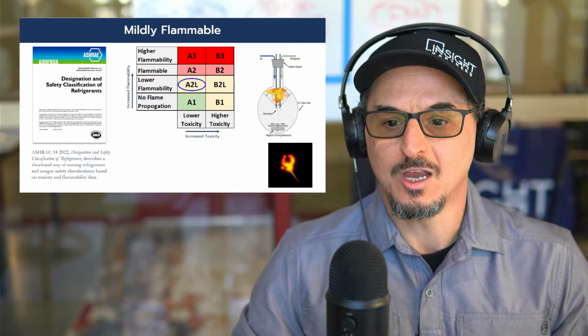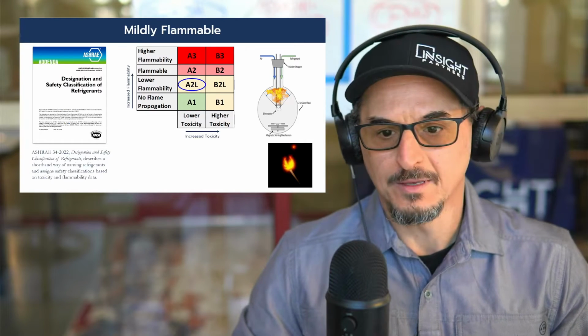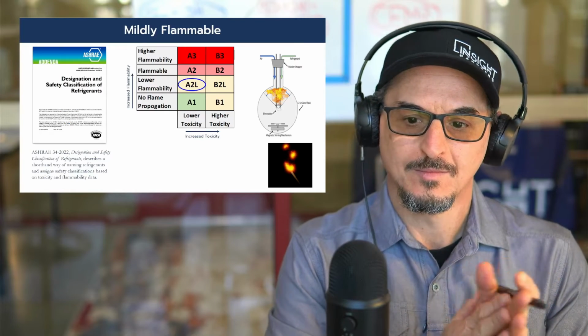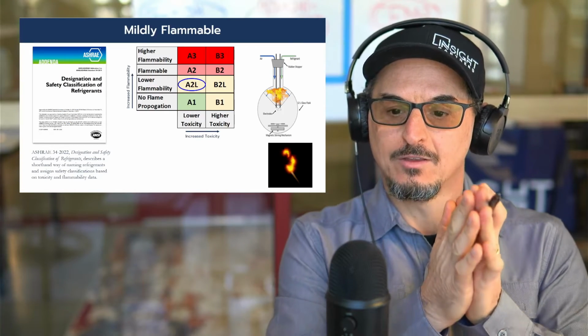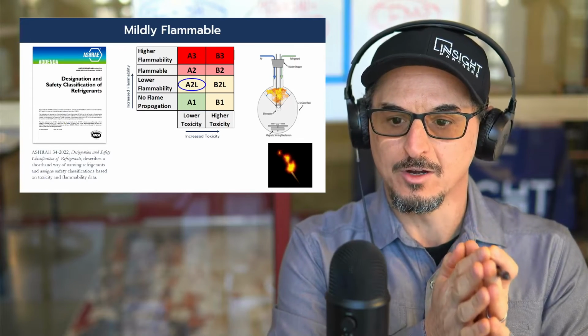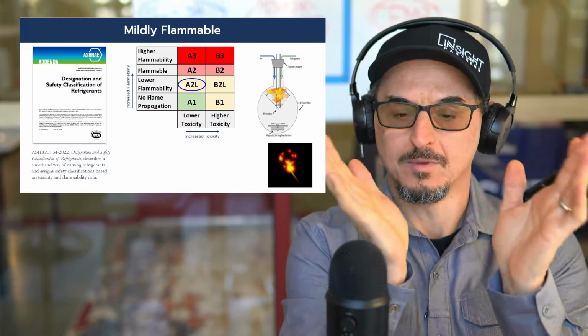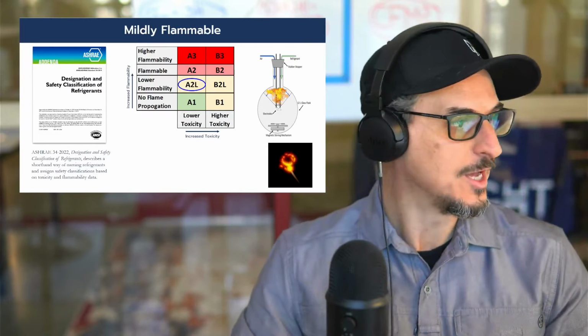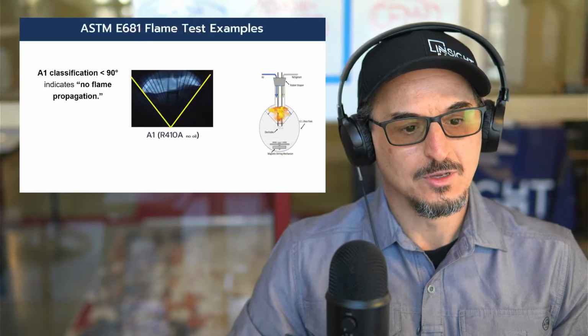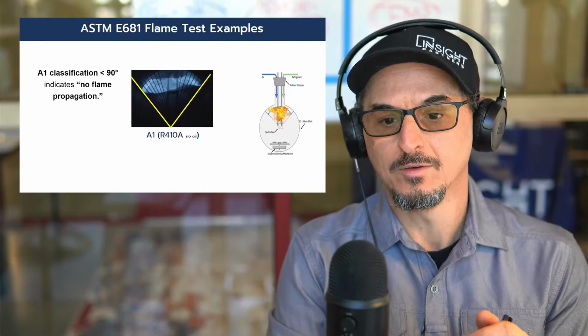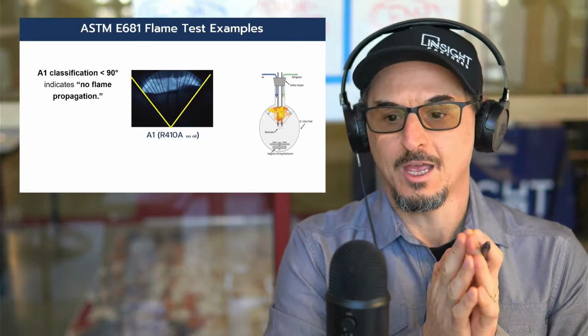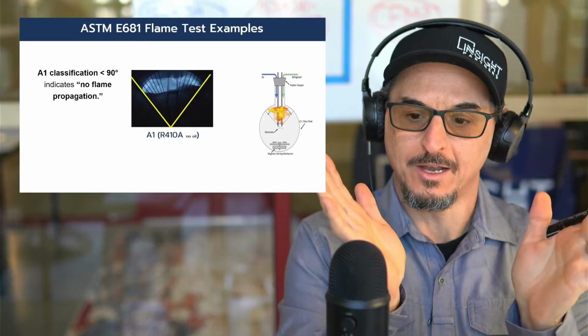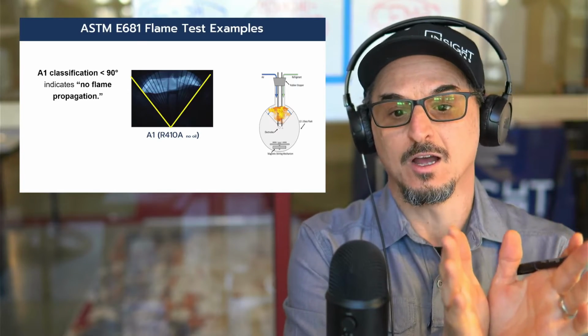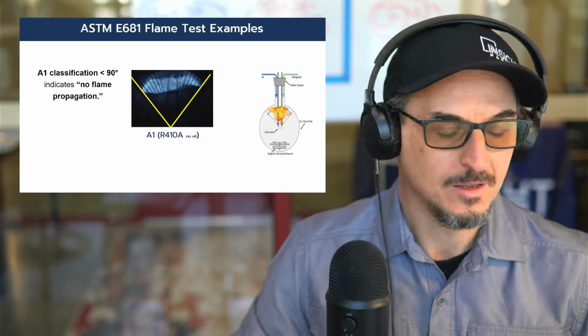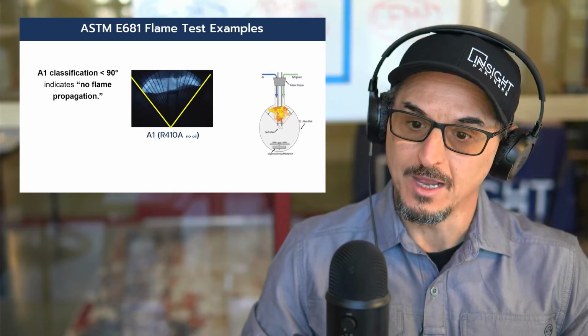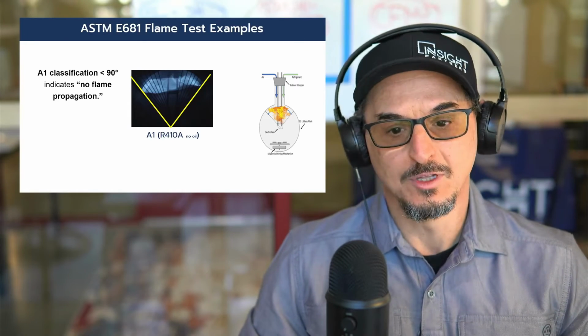If you see this test chamber by my head, this flask - there's a little flame animation underneath it. What happens is they put the refrigerant in there, mix it with air, stir it up, and ignite it. They measure the flame in terms of how much it spread - you can see those dotted lines, something like this. This is an actual photo of a test. At the 90 degrees, if the flame ignites and doesn't arc past the 90 degrees, it's classified as no flame propagation, which is below A2L.